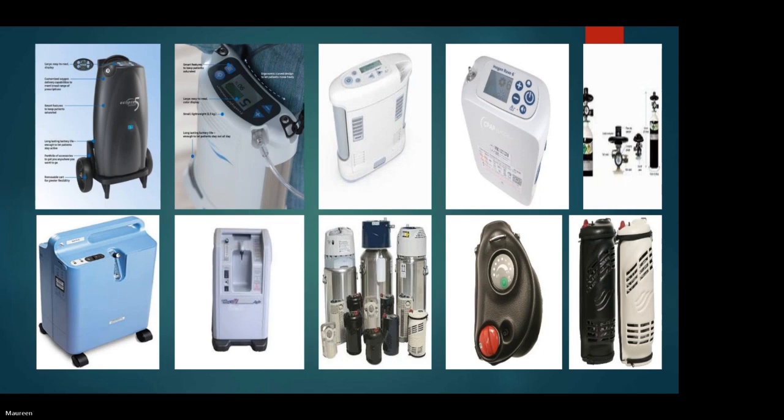Now, moving along the top row, you'll see 3 devices that all look fairly similar, and they are relatively similar. These are what you call portable oxygen concentrators, or POCs, and they only give pulsed setting of oxygen. And only one of them can go up to a maximum of setting 6, and that's the Inogen Rove 6. The other 2, which is called Caire FreeStyle, and the Inogen G3 or G5, they can only go up to setting 5 pulsed flow. Okay, so there are limitations with these machines as to who they are, well, useful for in terms of benefiting patients.